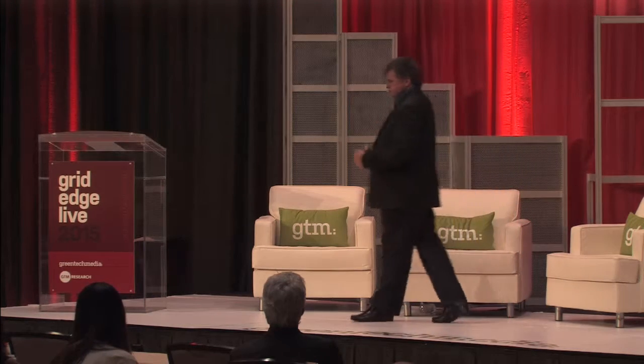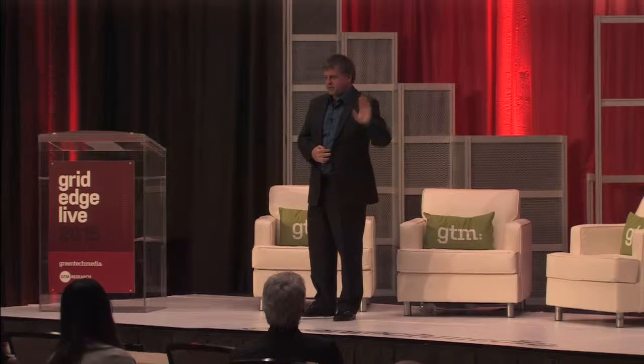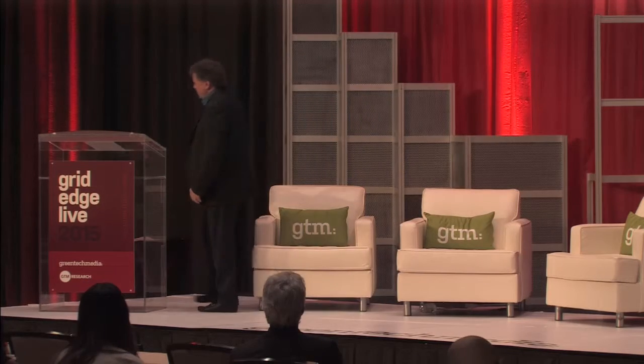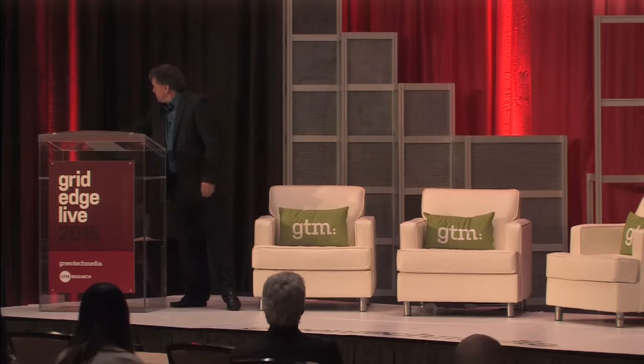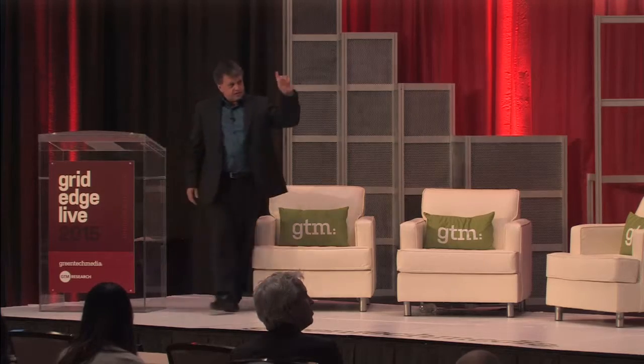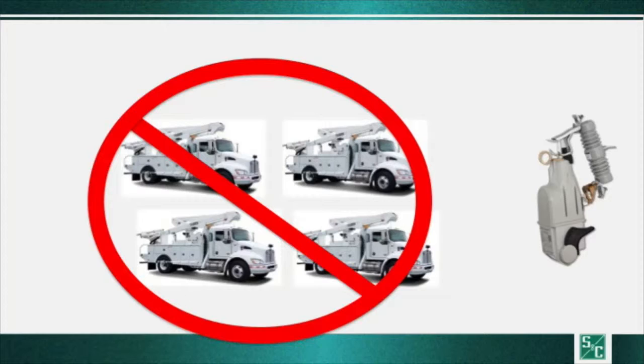And thirdly, the reclosers that have been around for years, they weren't always all that inexpensive. You install them, you've got to maintain them, there's a lot to it. What has made this more viable for FPL is a cutout mounted recloser that they're able to quickly put in place of the fuse that they've got, and a more economical recloser at the same time. In this particular case, if they save just 4 truck rolls, they pay for that recloser.